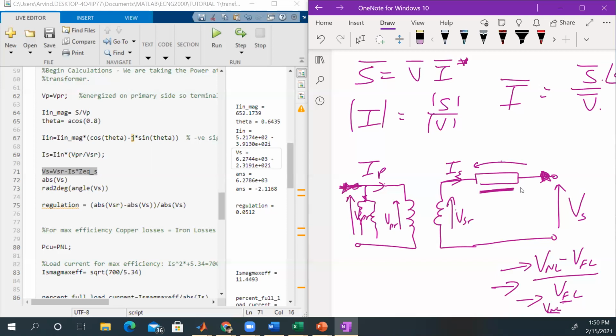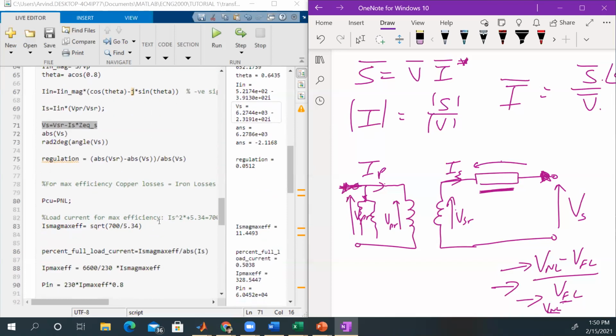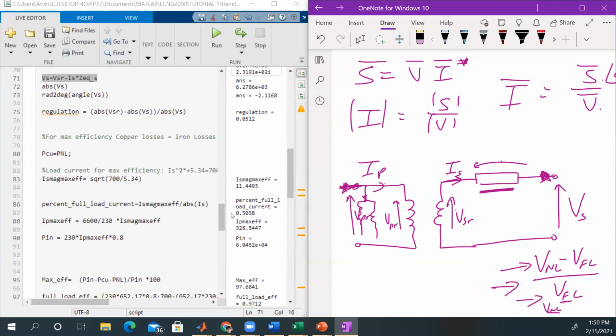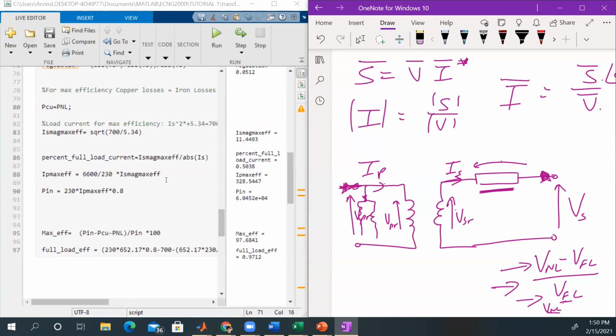Good. So we have the regulation here that we calculated at 5%, 0.0512. And the last thing we have to do is find the efficiency, or rather find the load current for maximum efficiency.